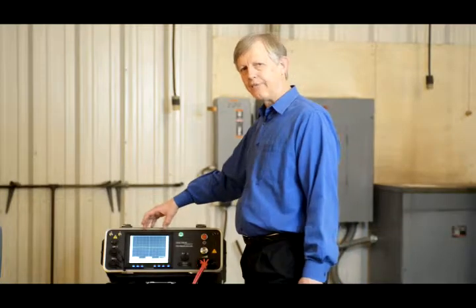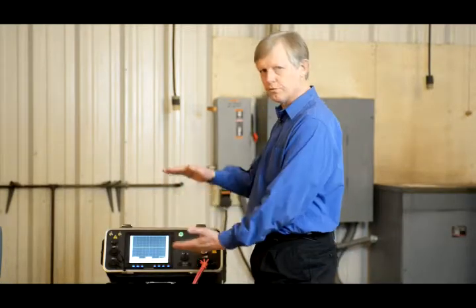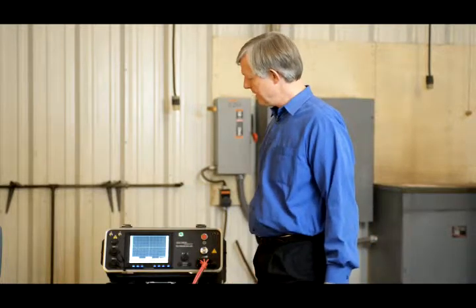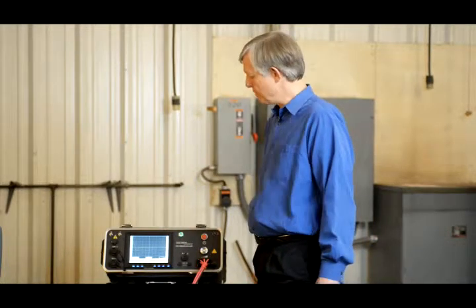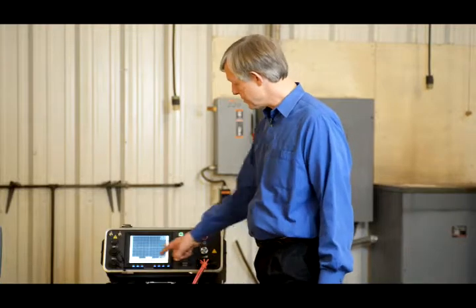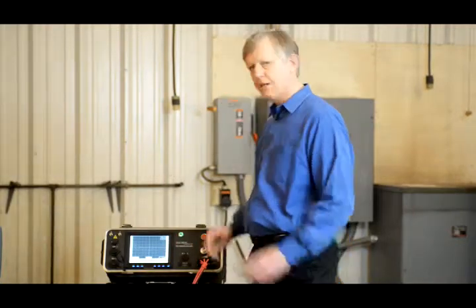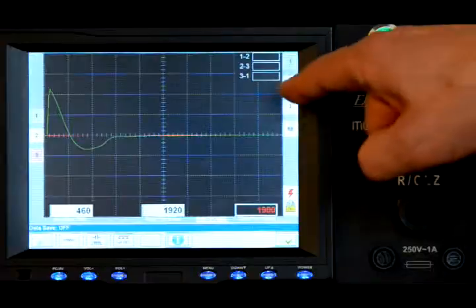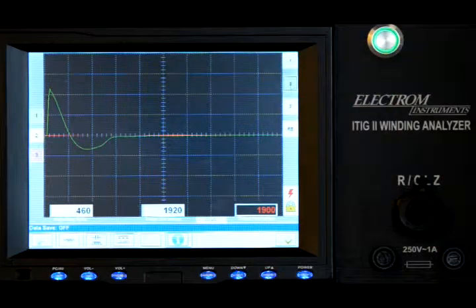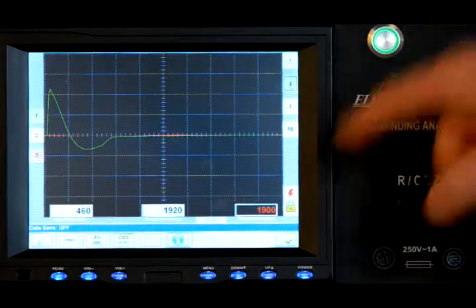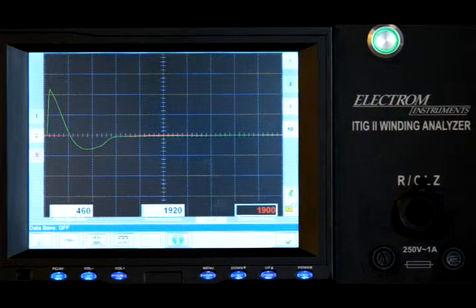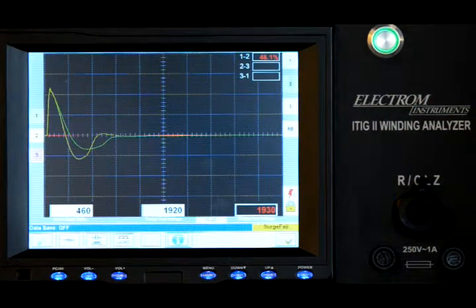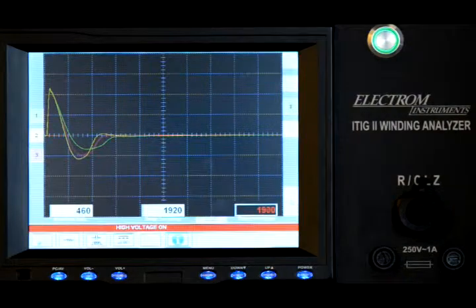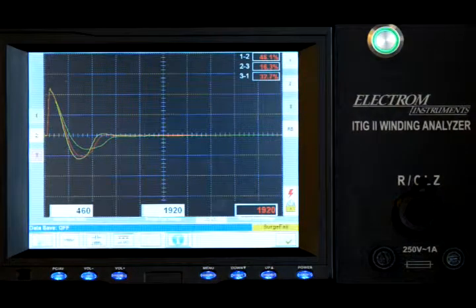The tester automatically finds what the sweep should be and what the voltage range should be, and drives the voltage up to the prescribed voltage, which is 1920, and shuts the test off. To test the next coil, we click on 2. I have to unlock it. Click the start button. We go to phase 3. Unlock, click the start button, and the test is done.